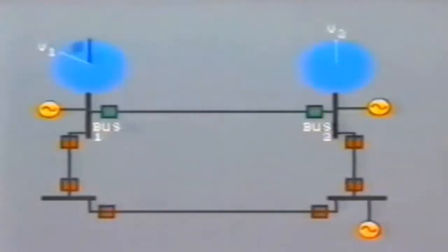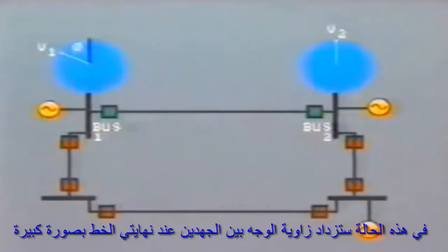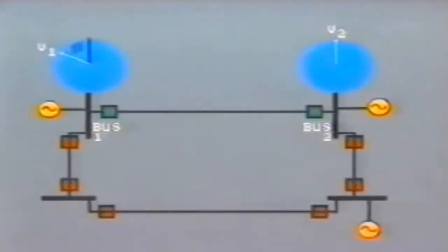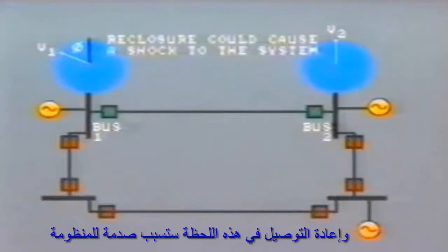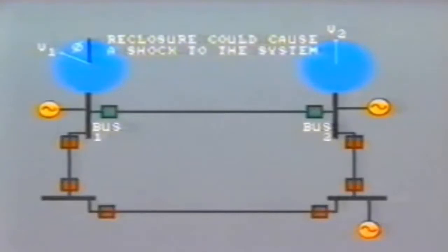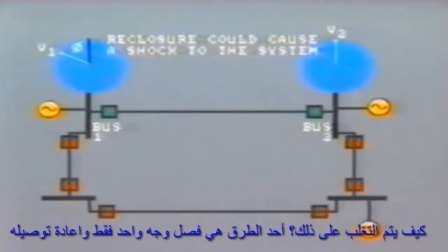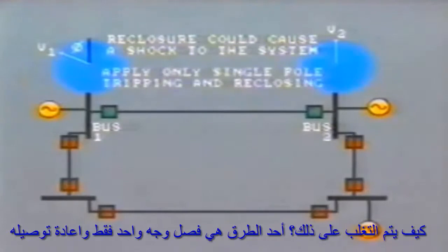The relay then attempts a second reclosure with time delay. In this situation, the phase angle between voltages at either end of the line may be quite wide, and reclosure at this point could cause a shock to the system. How can we get around this? Well, one method is to apply only single-pole tripping and reclosing.